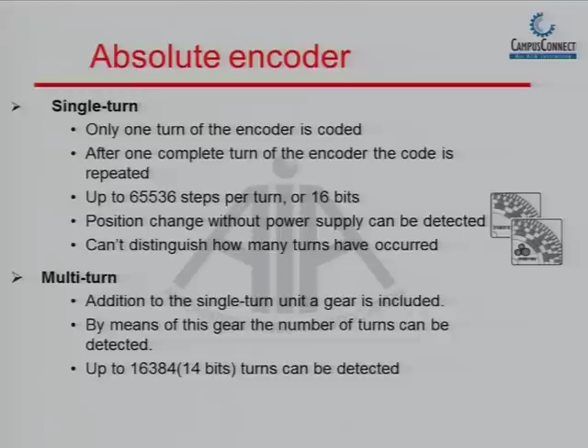Again, there are two types: single-turn and multi-turn. In single-turn, after one turn the encoder will reset, and you have to start all over again. In multi-turn, you can go up to a number of turns. The total number of turns is 14 bits, so you can go up to 16,384 turns before the encoder resets to 0.